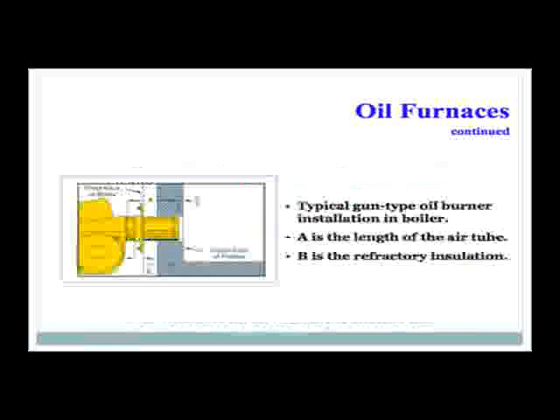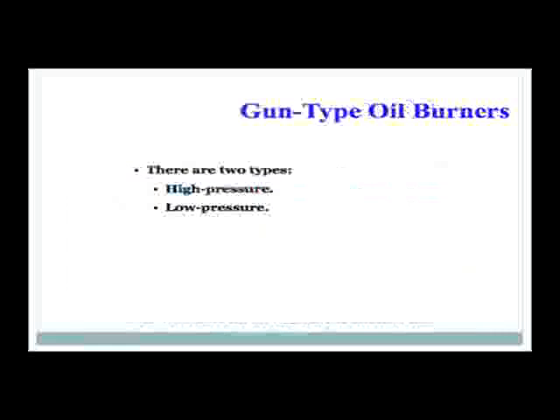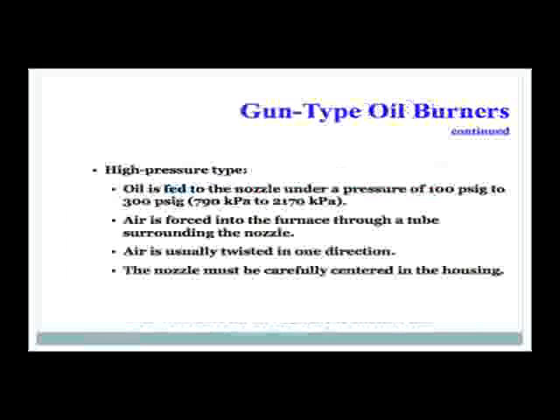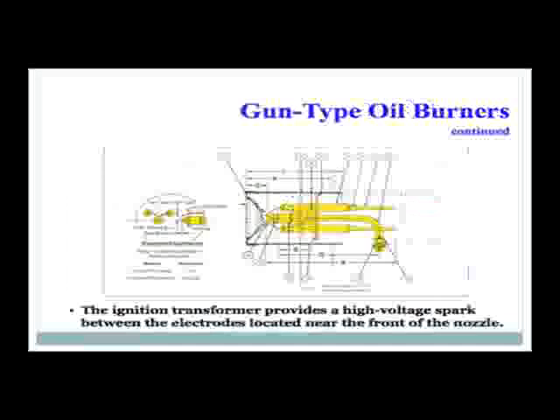A typical gun oil burner installation is shown in this picture. 'A' is the length of the air tube, and 'B' is the refractory insulation. There are two types of gun-type oil burners: high pressure and low pressure. In the high-pressure type, oil is fed to the nozzle under pressures between 100 PSI and 300 PSI. The air is forced into the furnace through a tube surrounding the nozzle and is usually twisted in one direction. The nozzle is centered carefully in the housing. The ignition transformer provides a high-voltage spark between the electrodes near the front of the nozzle. In this picture, number 13 is the nozzle, 14 is the electrodes, and 7 is where the ignition transformer connects to the electrodes.